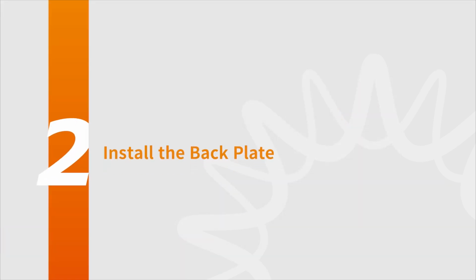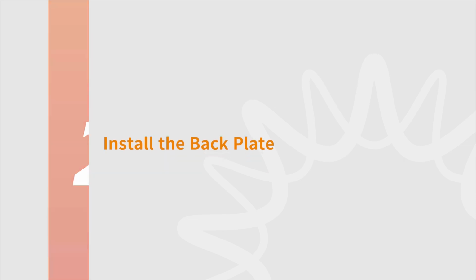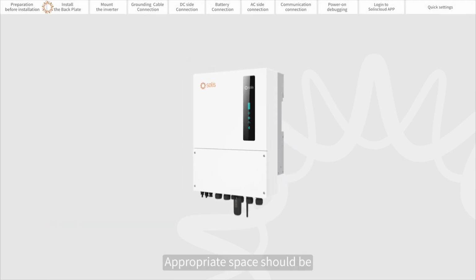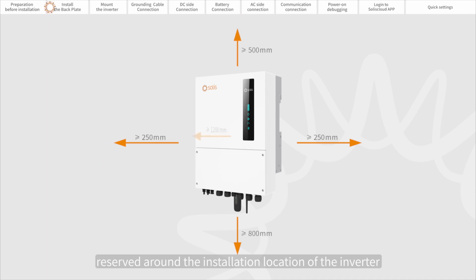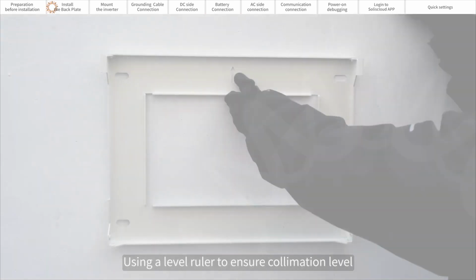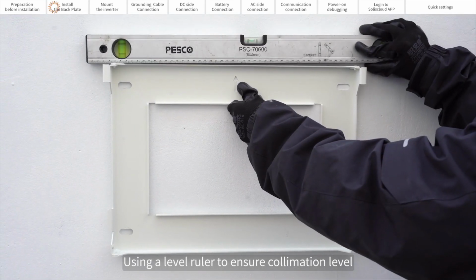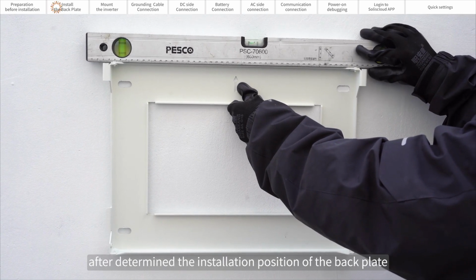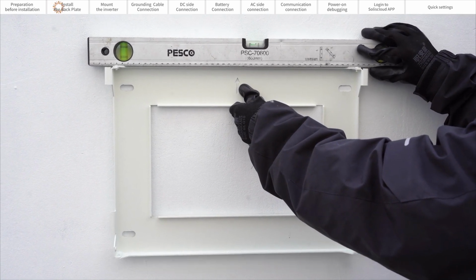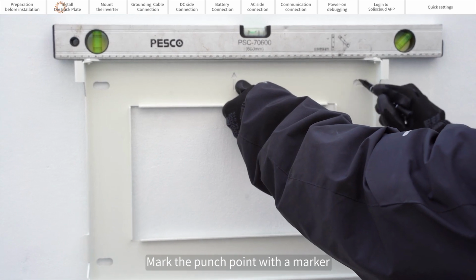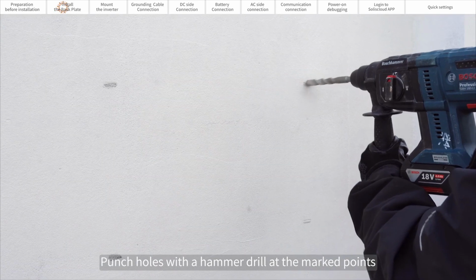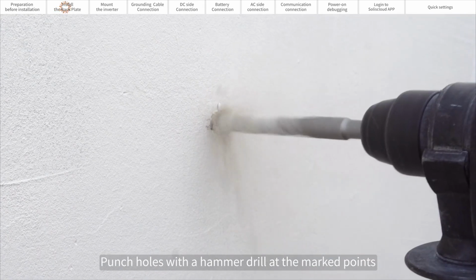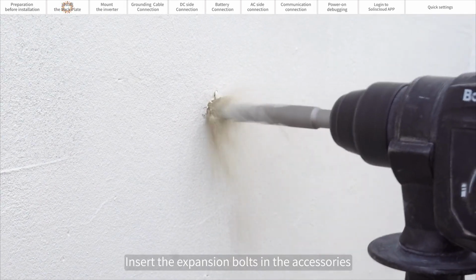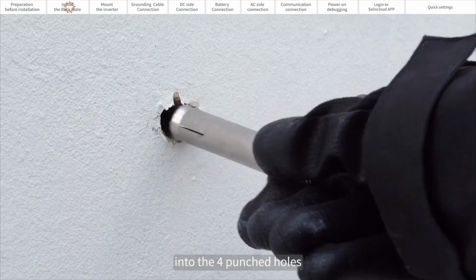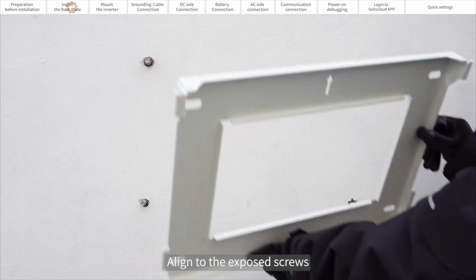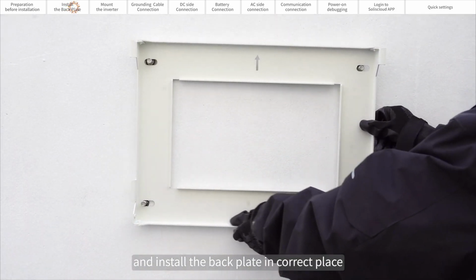Part 2. Install the backplate. Appropriate space should be reserved around the installation location of the inverter. Use a level ruler to ensure collimation level and determine the installation position of the backplate. Mark the punch points with a marker and punch holes with a hammer drill at the marked points. Insert the expansion bolts in the accessory into the 4 punched holes, aligned to the exposed screws, and install the backplate in the correct position.